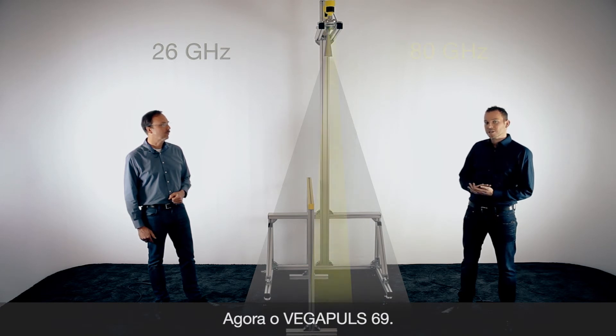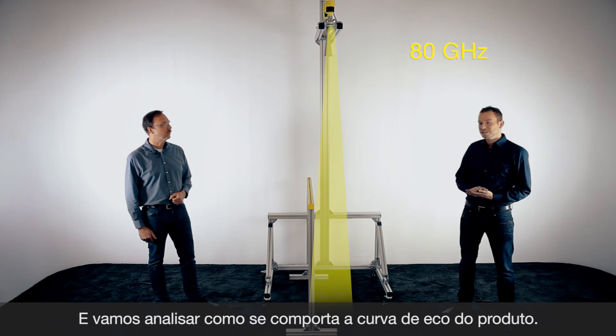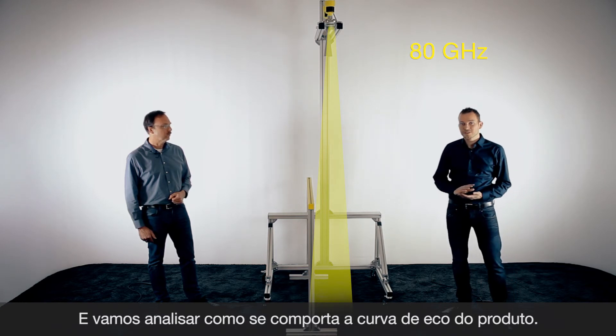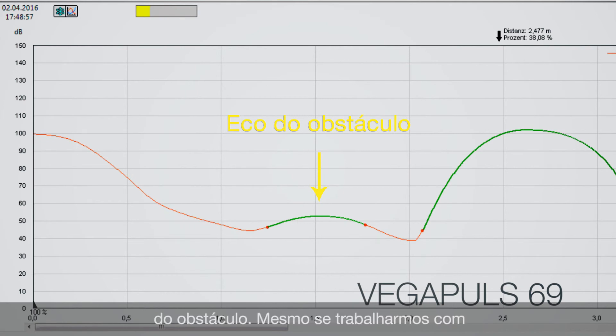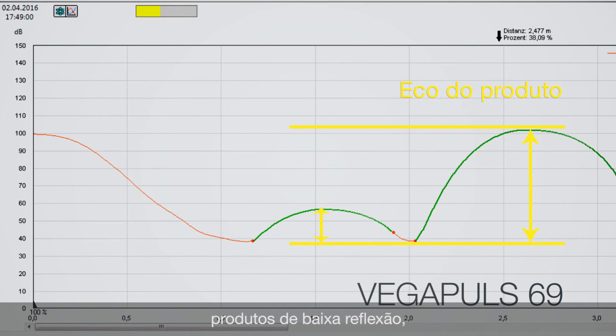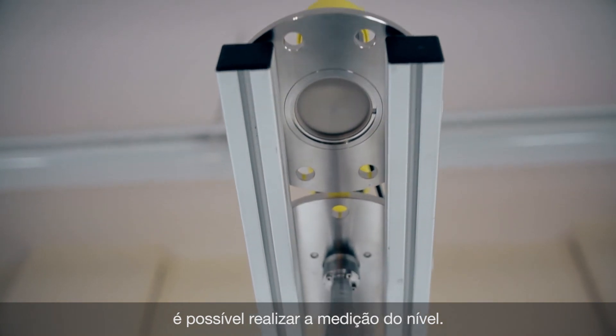With this short distance we are now also hitting the beam angle of the 80 gigahertz sensor. Let's have a look at the echo curve. You can see a slightly false signal, but it is very small and you still have a very good product echo. So in this case, even if you have a product with bad reflecting conditions, you still get a very safe measurement with the VEGAPULS 69.